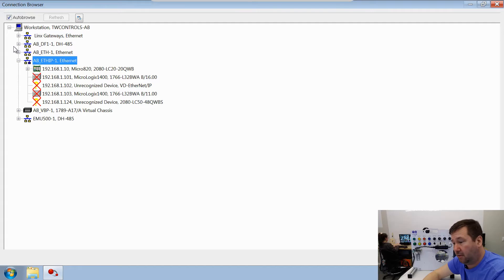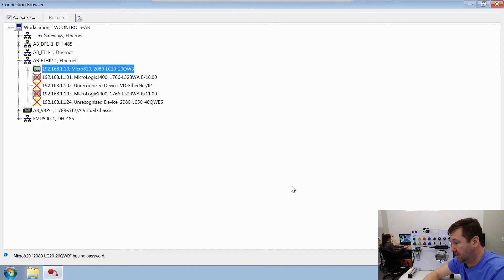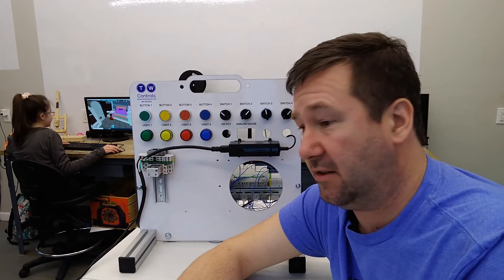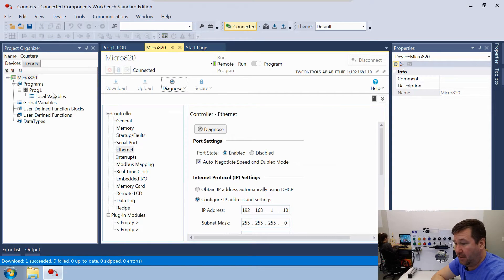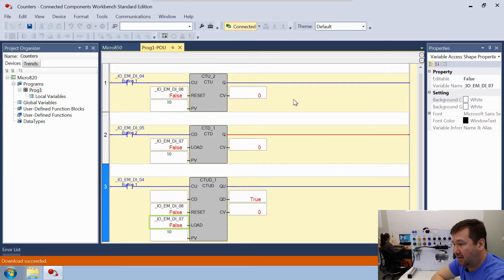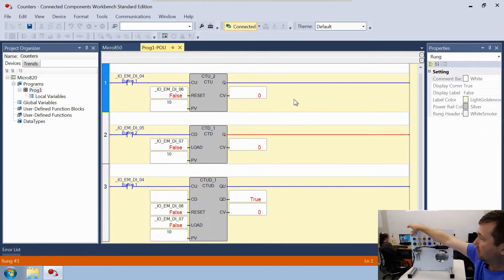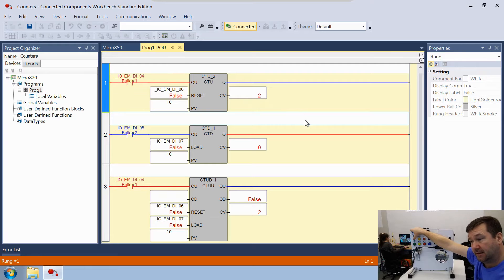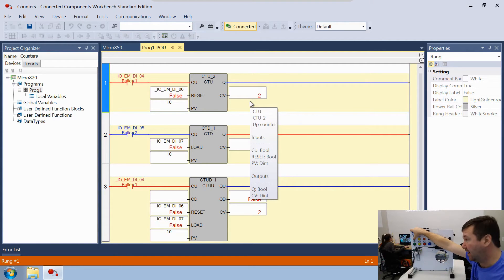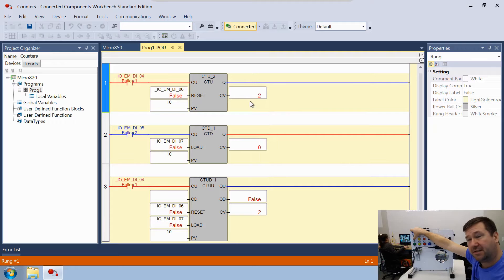I'm not going to go through all the steps for configuring communications — we have videos on Ethernet and serial, so check the description for links. Make sure you put the processor back in Run mode after downloading. Let's focus on the count-up counter in Rung 1 first. Press Button 1 and the counter value goes up to 1. Note: if you press and hold the button it only goes to 2 — it doesn't keep counting; it only counts each new button press.